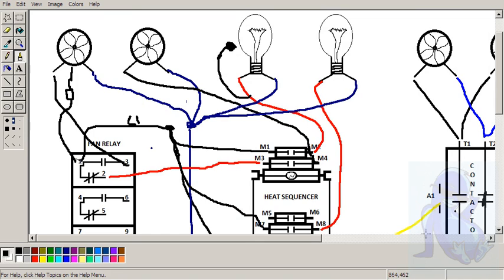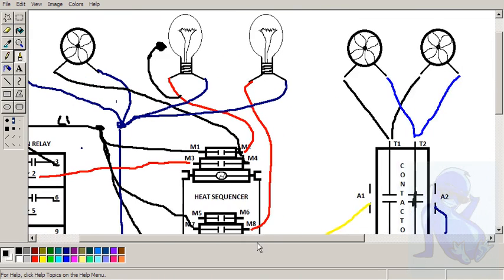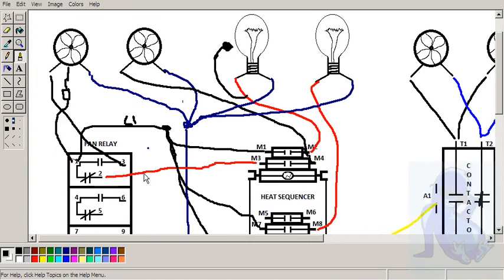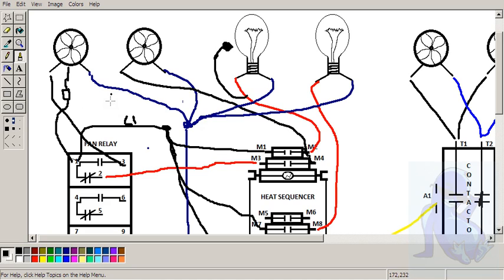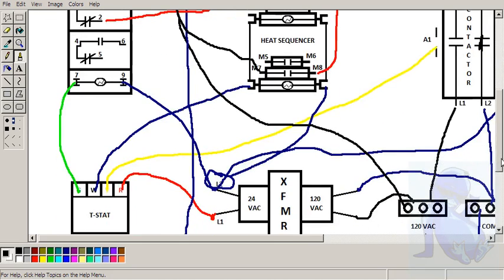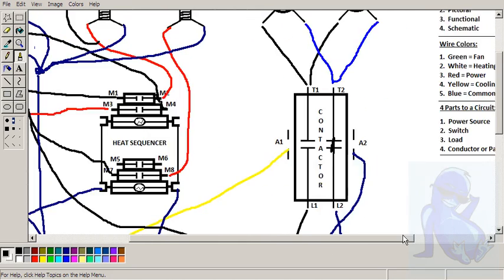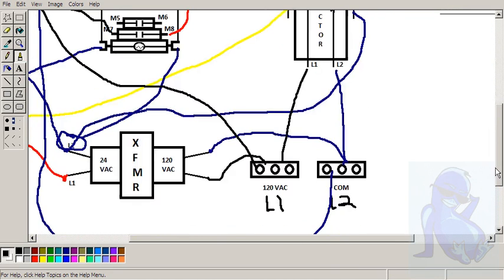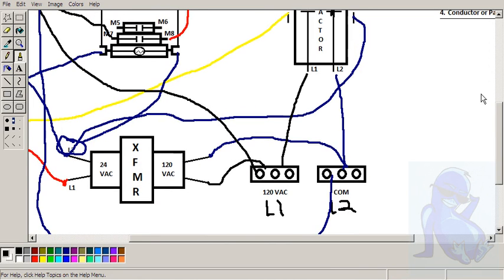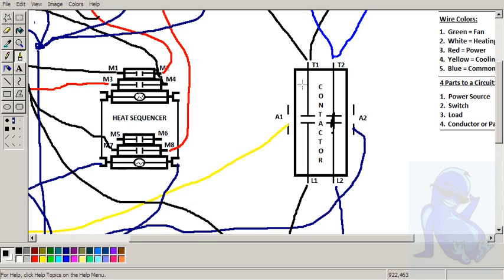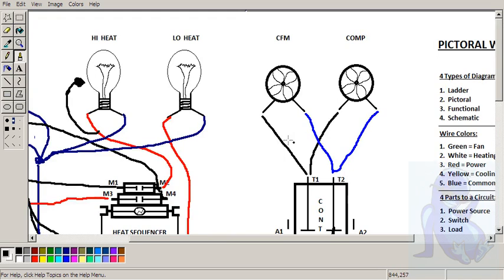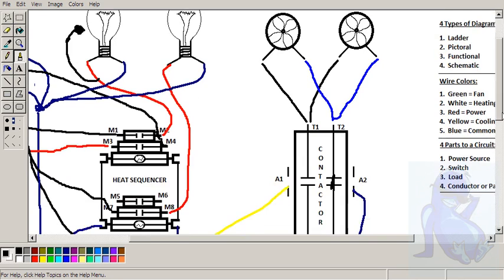You could have another one that works in a way that senses for water somewhere. Maybe underneath the evaporator pan you sense that water is not draining properly. And it could be out there as well. And you could decide to have that cut off the whole system. But anywhere you want to tie it in there, you can have it cut off the compressor alone. You can have it cut off the condenser, but you basically tie it into the circuit. And have it open up when it senses too much water.